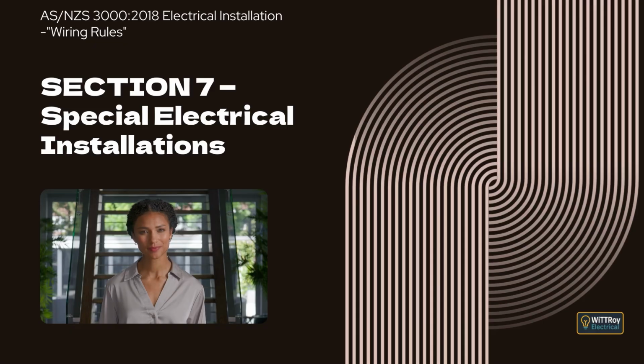It states that wiring systems for safety services must be able to keep supplying electricity to equipment even when exposed to fire. It also explains that a power source intended for safety services must not be used for other purposes if doing so would reduce the availability of power for safety services. Where safety services need to operate during emergencies or when the normal supply is lost, it may be necessary to automatically disconnect non-essential equipment so enough capacity is available for safety services. An exception is explained for certain fire detection, alarm and intercom systems that use compliant battery backup supplies.